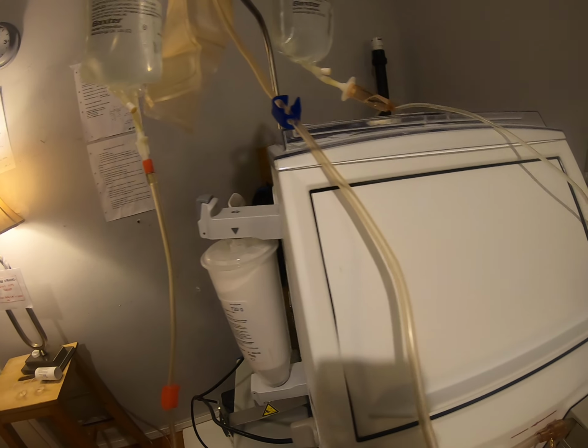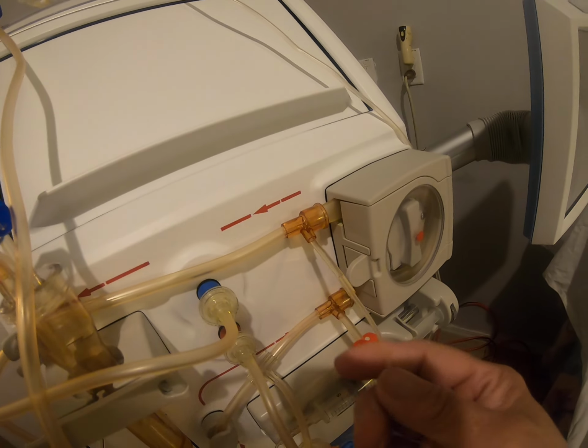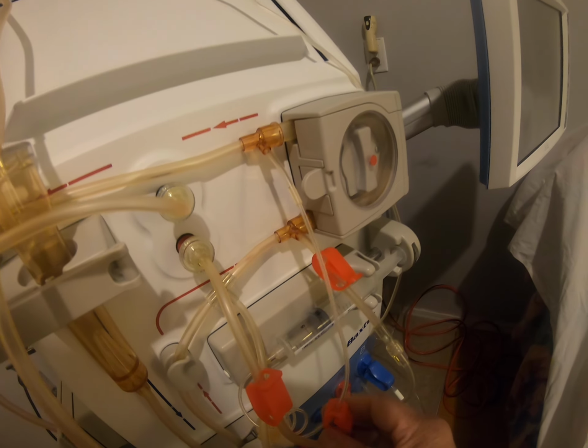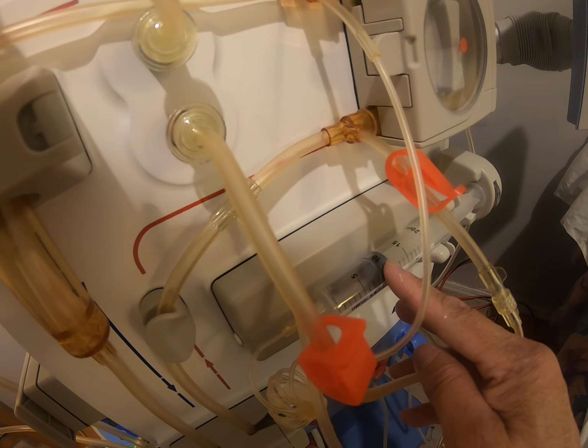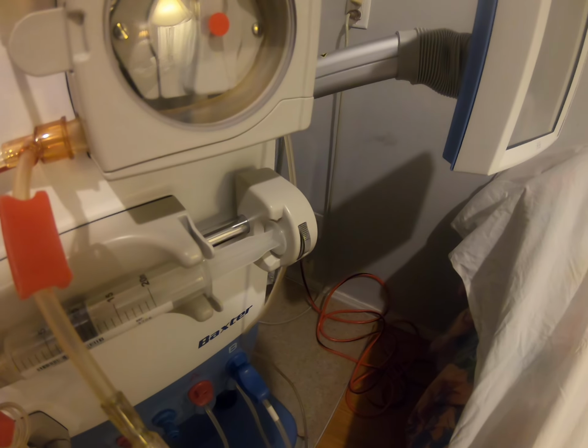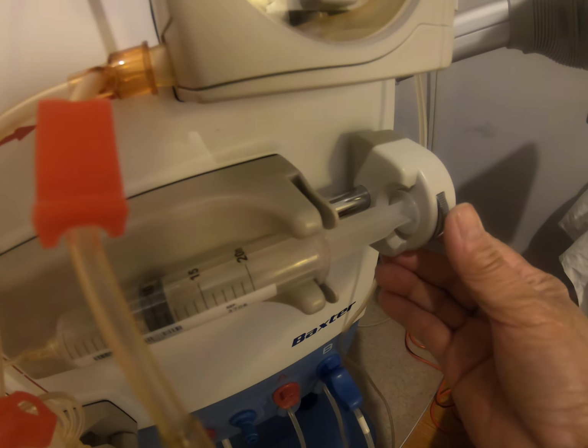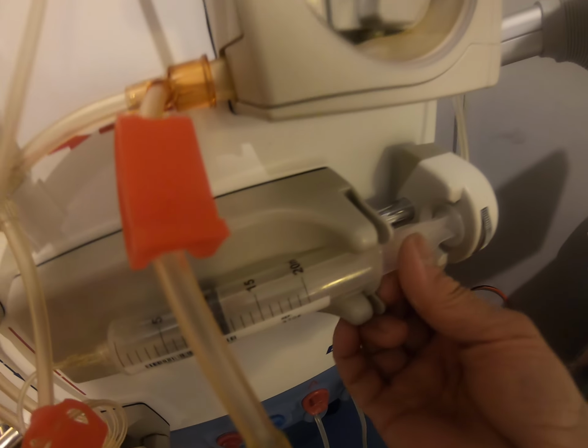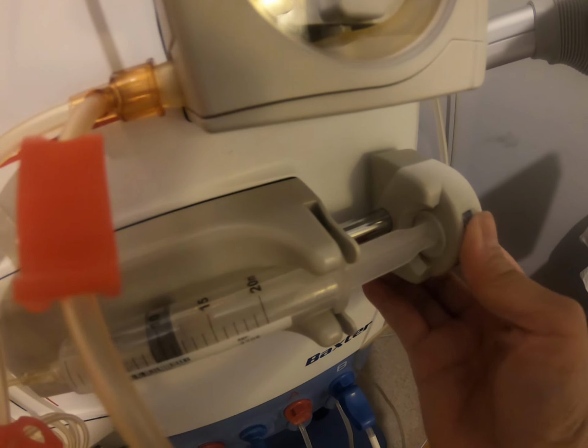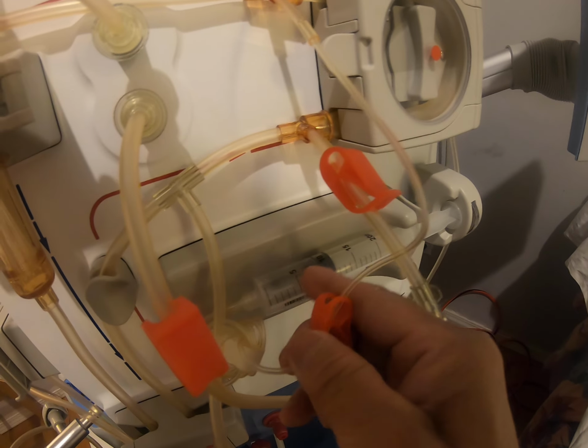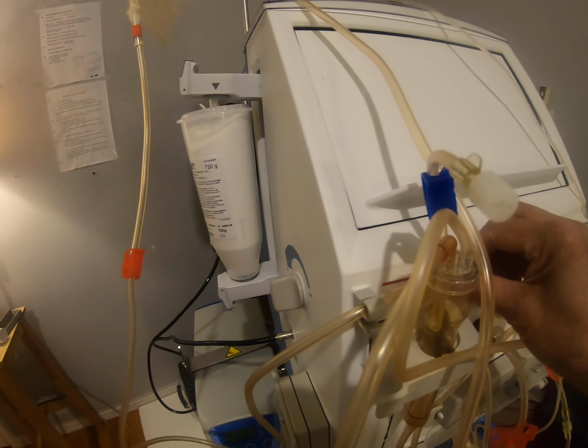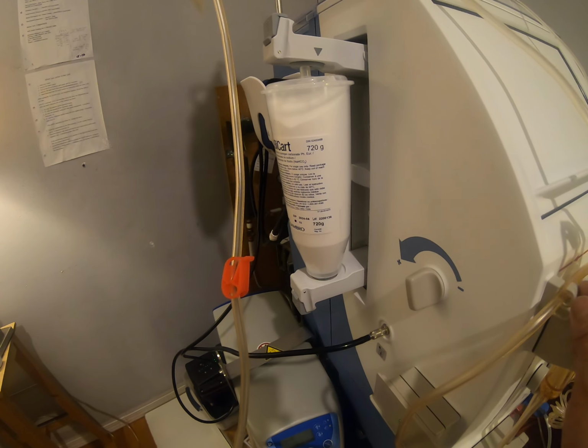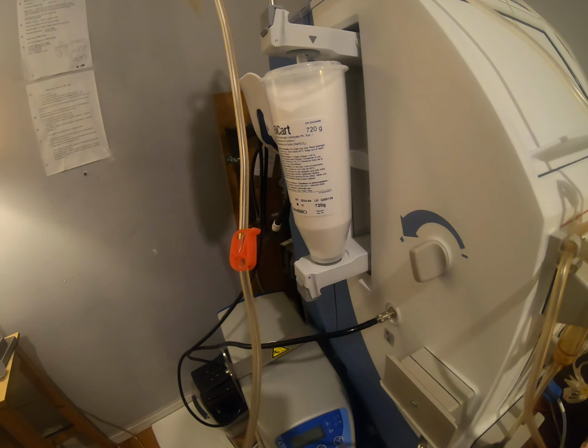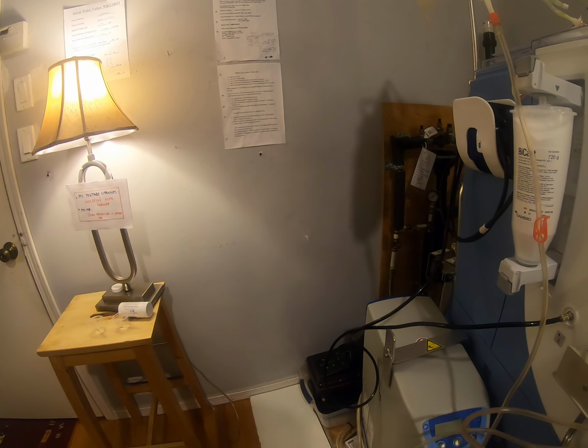Okay, and then after the blood pump here, we see there's another tubing, and that goes to the heparin. We normally put 10 cc in here, and this is where you put the heparin. There is a lock wheel in here to release it so that you can remove or put it right here and then close back. The clamp of the heparin is open. After that, the tubing will go to the guide, and the tip of this part will go to the patient.